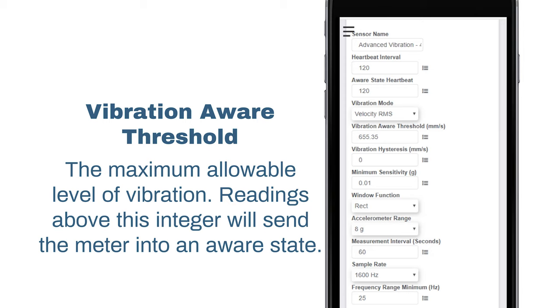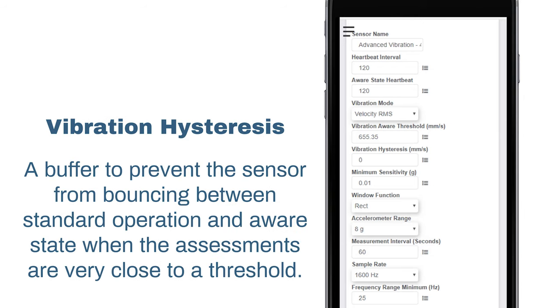Vibration aware threshold is the maximum allowable level of vibration. Readings above this integer will send the meter into an aware state. Vibration hysteresis is a buffer to prevent the sensor from bouncing between standard operation and an aware state when the assessments are very close to a threshold.